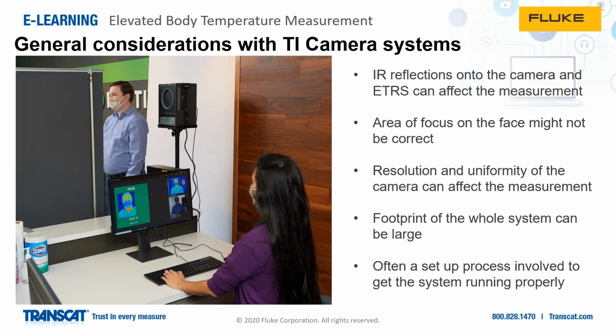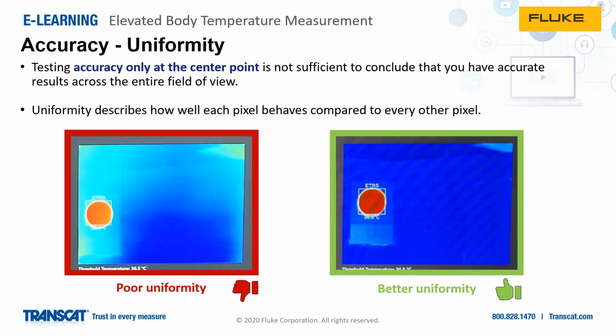Resolution and uniformity of the camera itself can affect the measurement, and we'll talk a little bit more about that. The footprint of the overall system, especially when compared to an IR thermometer, can be quite large, and often there's a lengthy setup process involved to get the system running properly. So talking about some of the considerations here, we'll start with accuracy, and under accuracy, uniformity. So testing accuracy only at the center point of your thermal imaging camera is not sufficient to conclude that you have accurate results across the entire field of view.